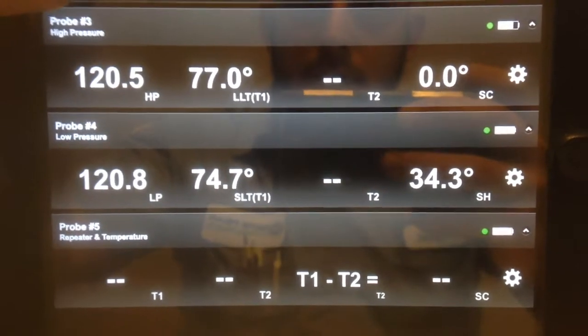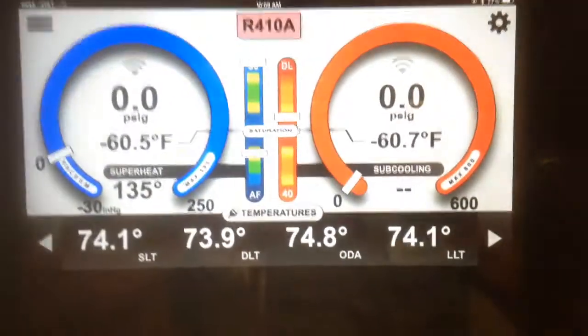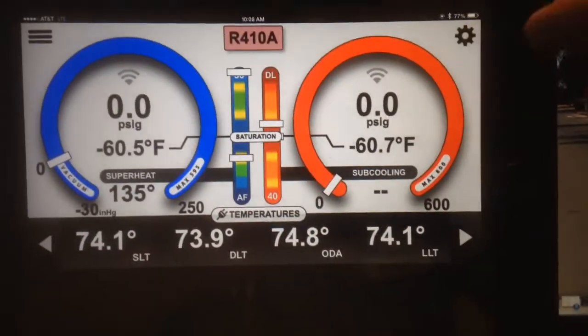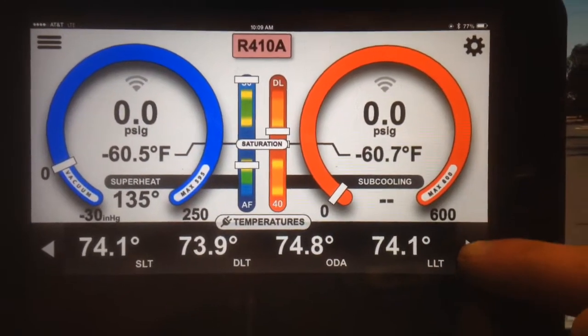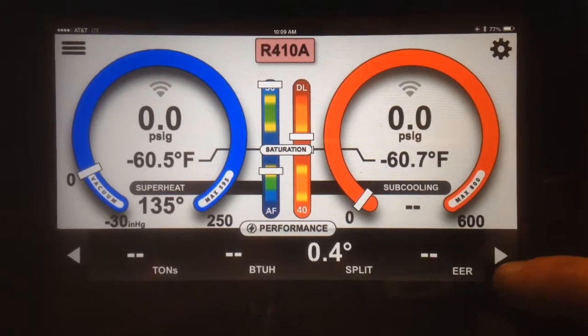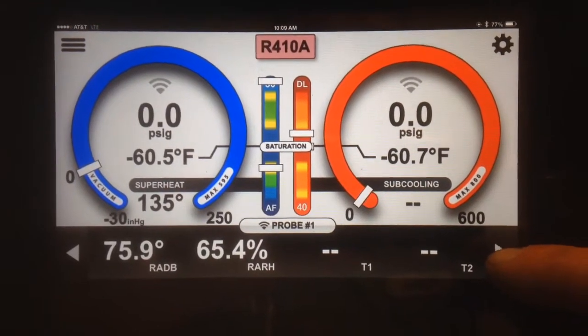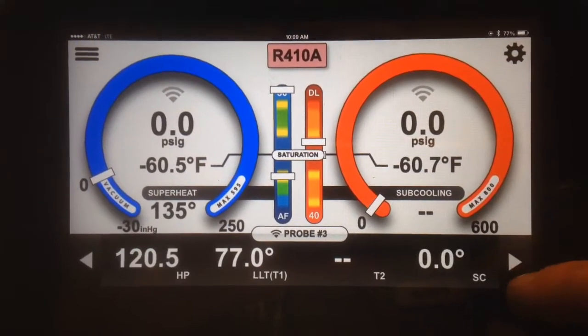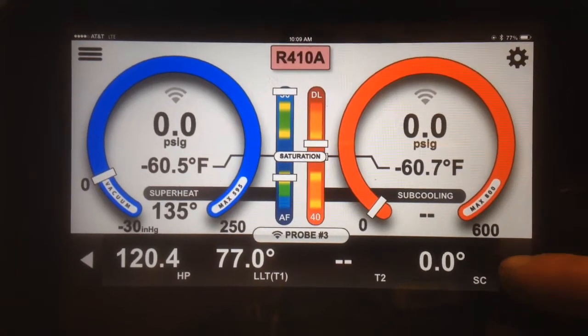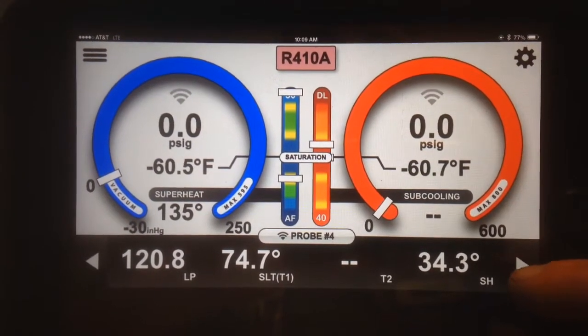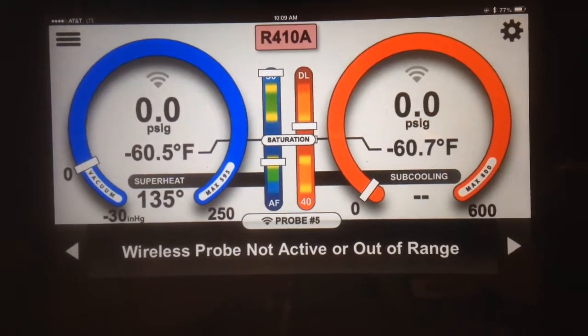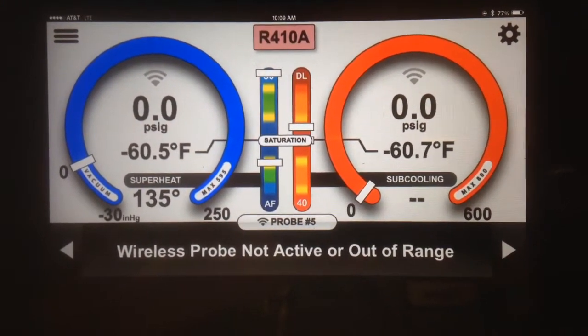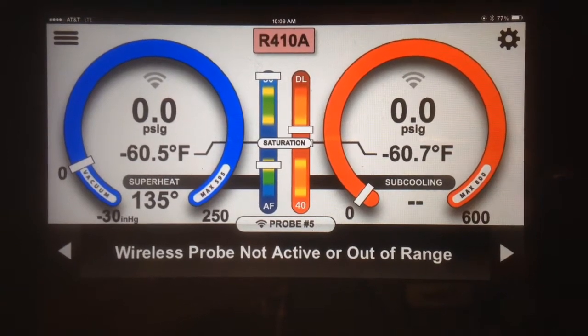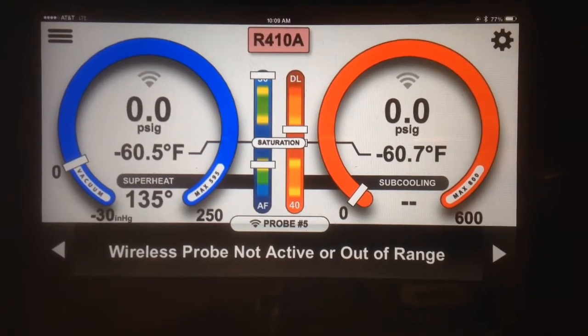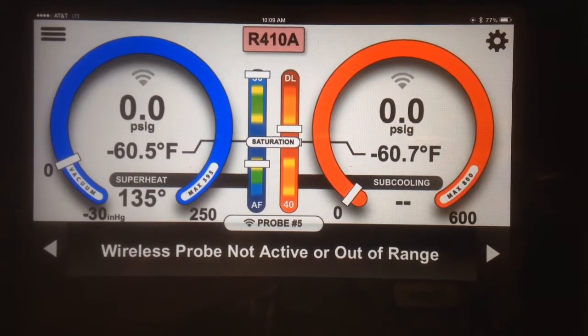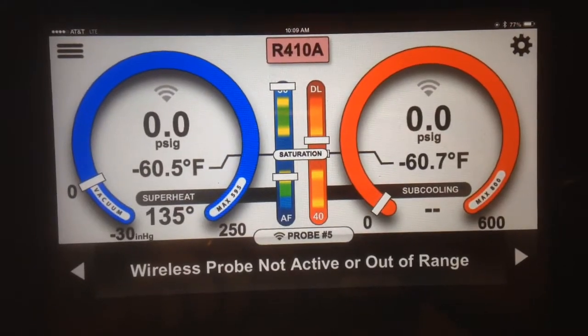Now, if we go back to the manifold, I wanted to point this out because it threw me for a loop for a second. If we go over to probe 5, there's probe 1, probe 2, probe 3, probe 4, and this is what probe 5 looks like. If I were to connect a strap lead to this probe, it would then show that information. I'm going to go ahead and tie into T1.